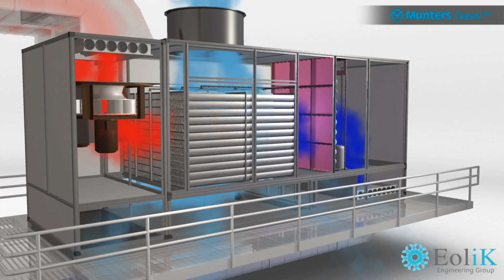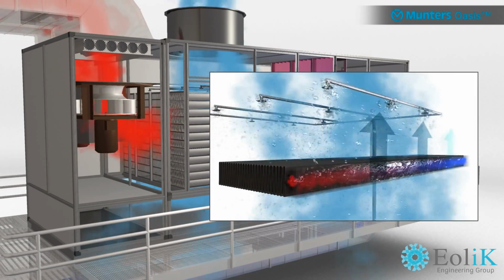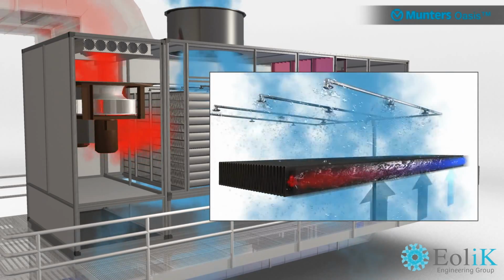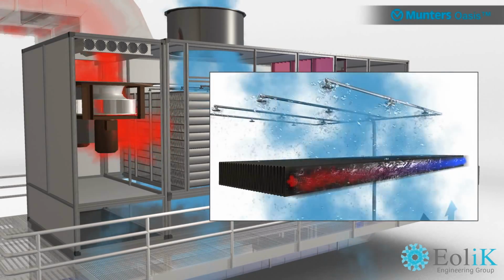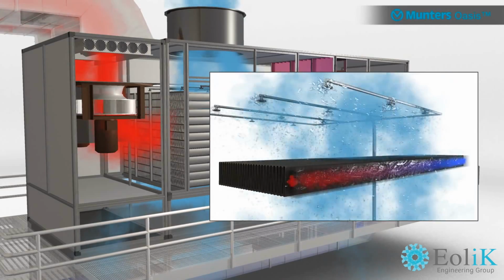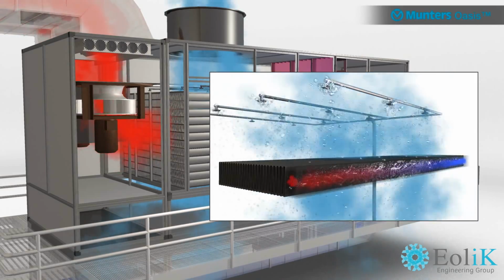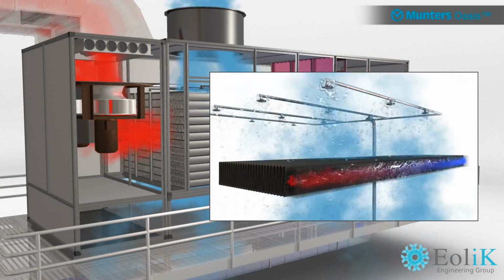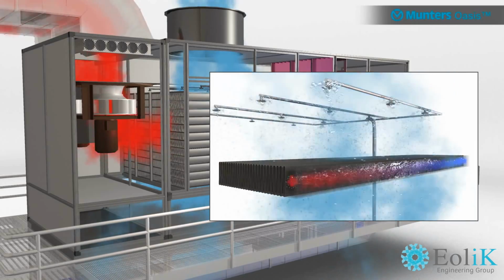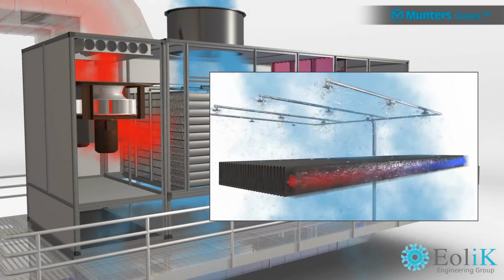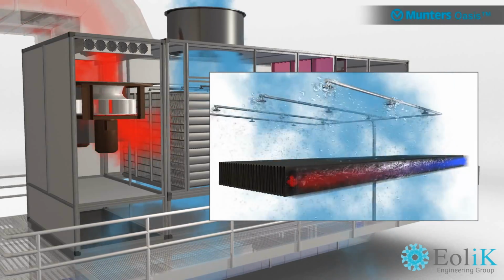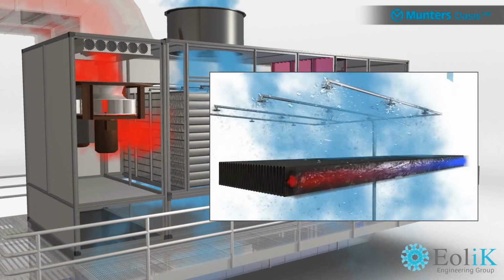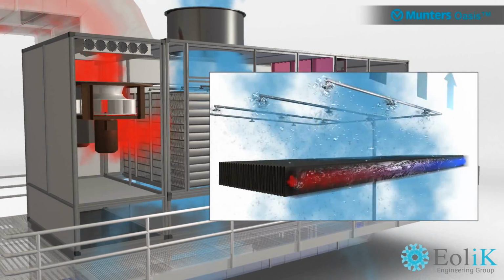Munters' innovative patented EPX evaporative polymer exchanger coats the heat exchanger's polymer surfaces with a film of water and chills the air to a lower temperature than can be achieved using only dry air heat transfer. The evaporating water film runs down the outside of the polymer tubes, accelerating the transfer of heat from the tubes to the outside air that flows between them.